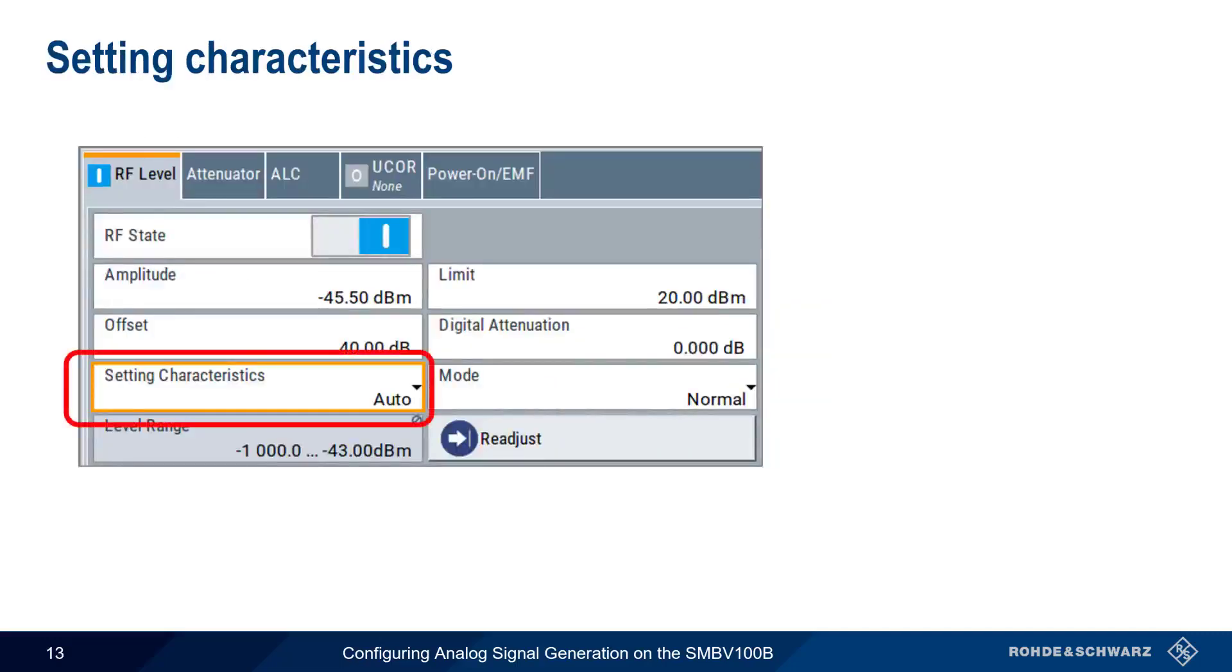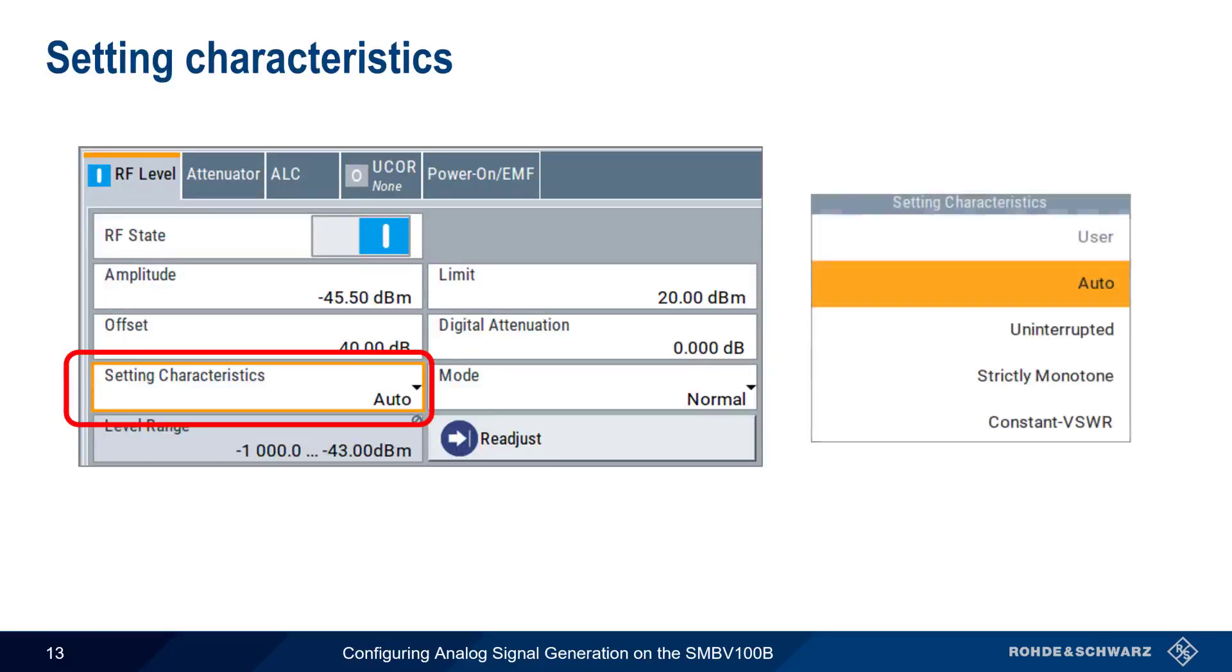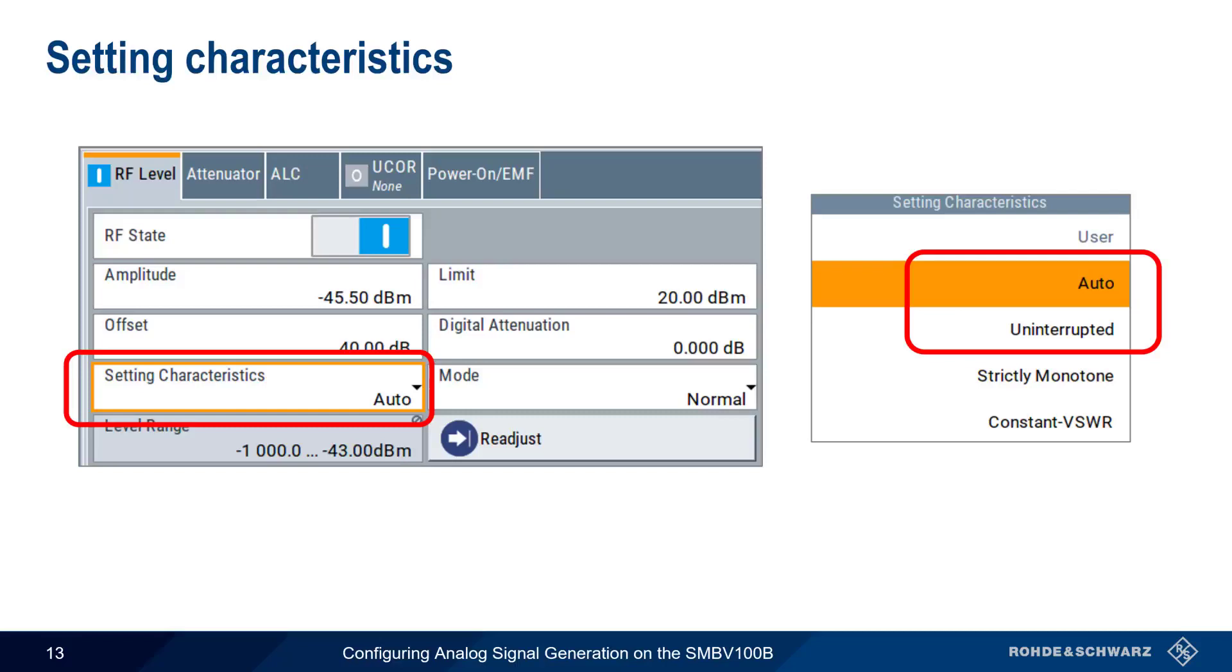Setting characteristics can be used to optimize the RF signal level behavior for different applications. Although there are numerous different setting characteristics, the two most important of these are auto and uninterrupted. Auto provides the fastest setting times and the highest dynamic range. However, the RF signal may be briefly blanked or turned off as we change level over this range. This is due to switching of the internal step attenuator. Uninterrupted mode, on the other hand, avoids this level blanking, but the level range is reduced. Note that even if we stay within this range in uninterrupted mode, blanking can still occur if our frequency changes.